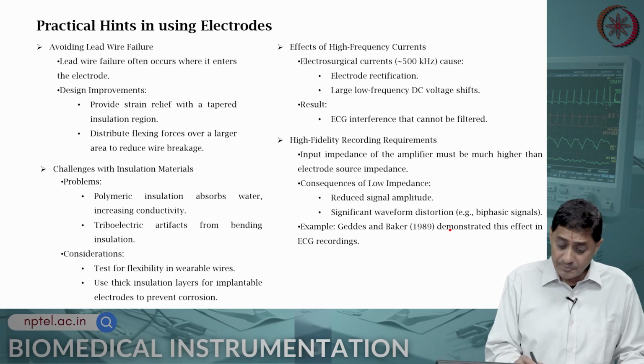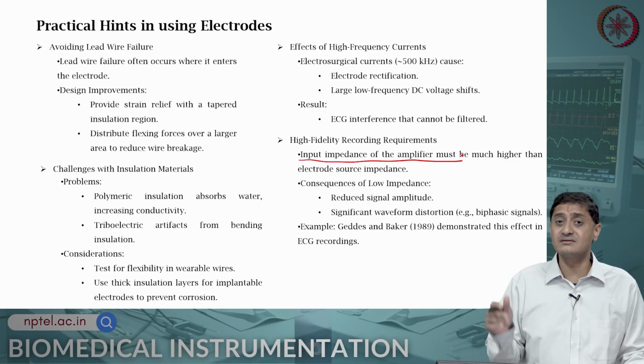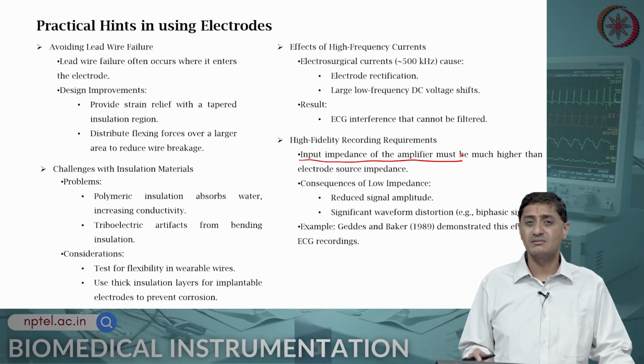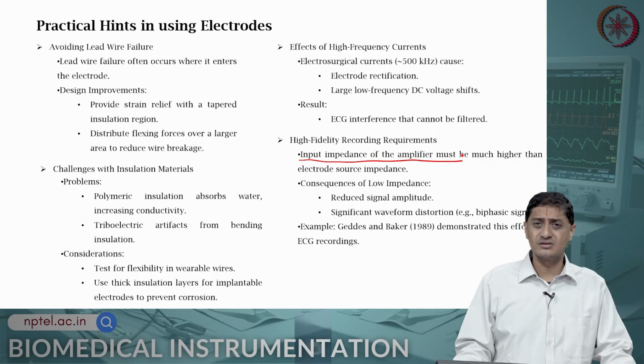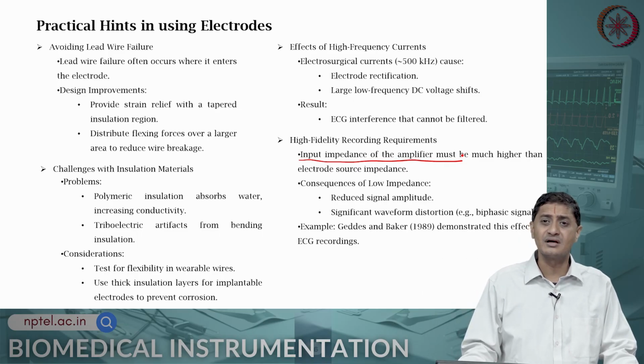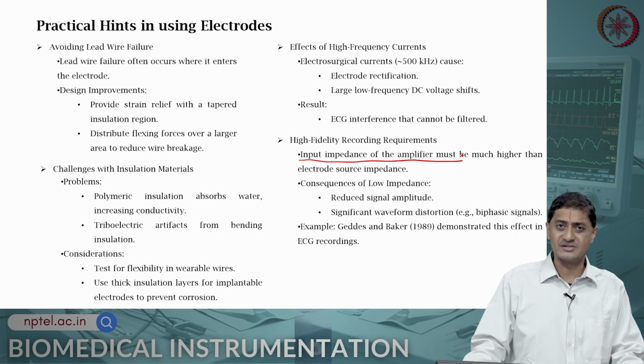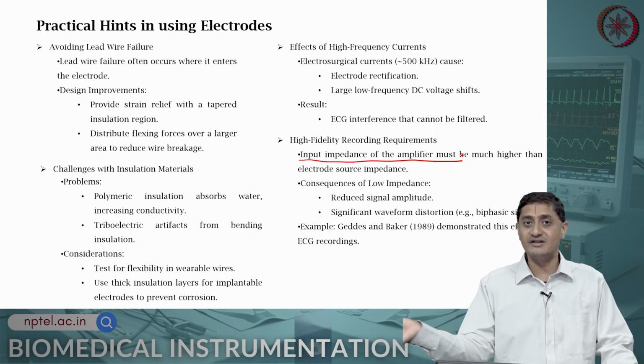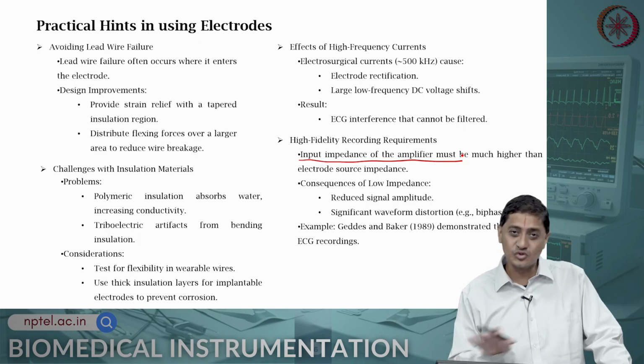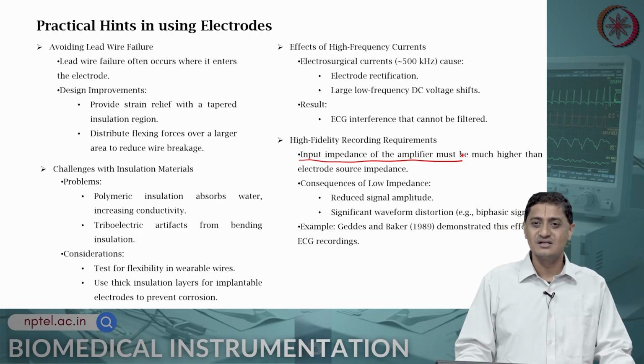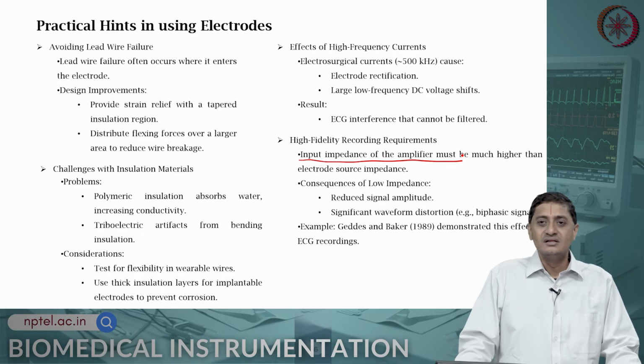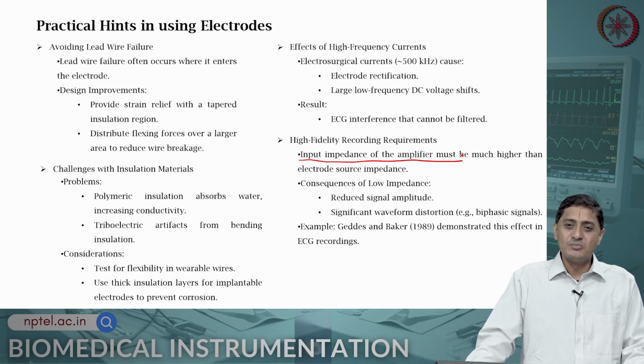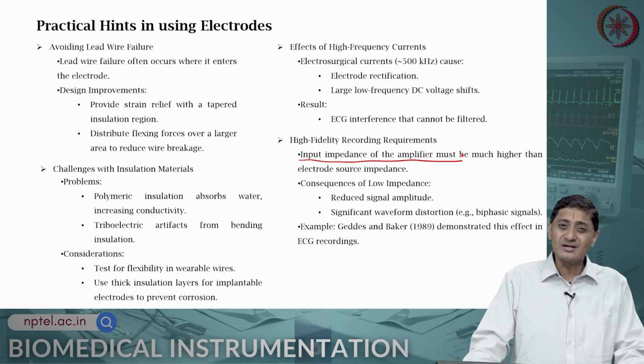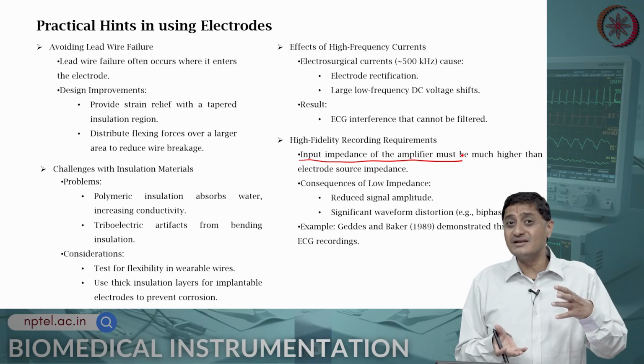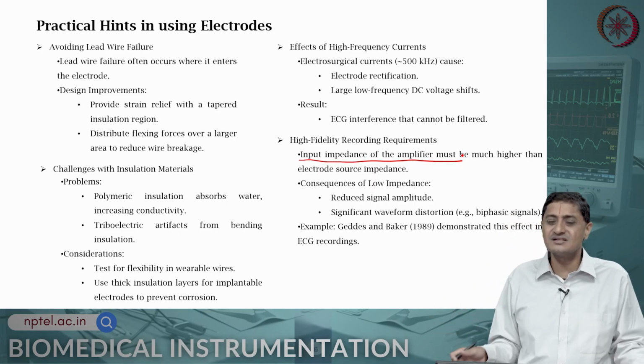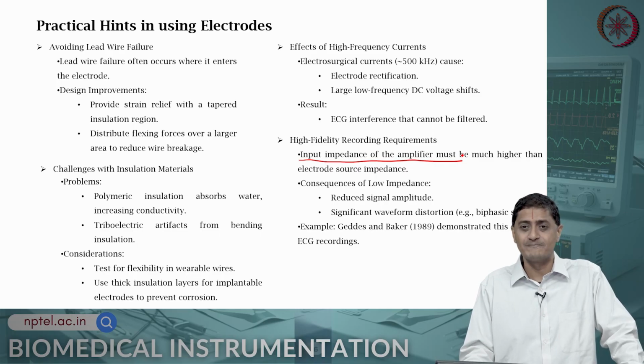What is high fidelity equipment? The input impedance of the amplifier must be higher than the electrode source impedance. It must be not just slightly higher, it must be orders of magnitude higher. Otherwise what will happen? Otherwise there will be loading, as in a voltage divider. Otherwise current will flow through the amplifier, which is not a desirable situation. If there is low input impedance, this essentially reduces the signal amplitude, and comparably the noise amplitude will be higher, and essentially this reduces the signal to noise ratio.